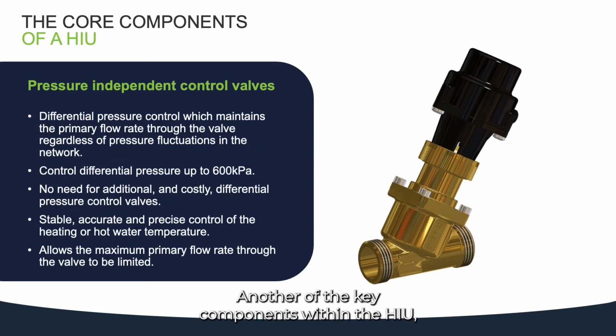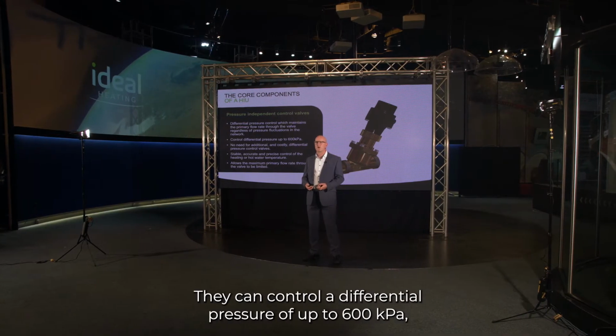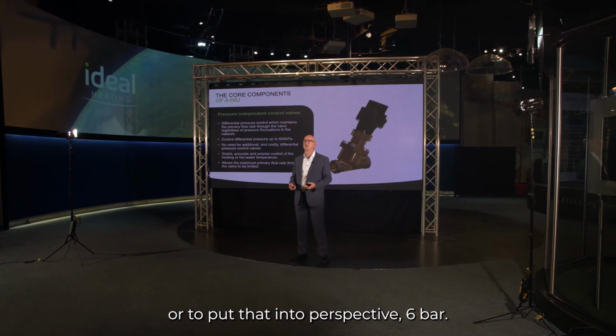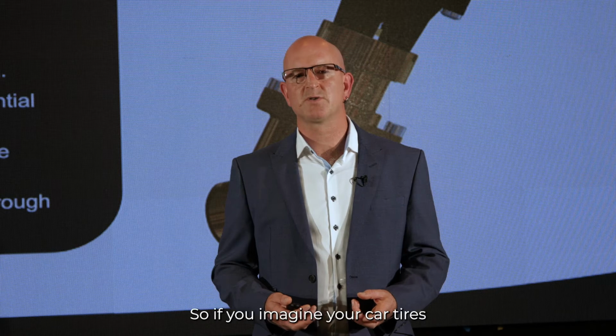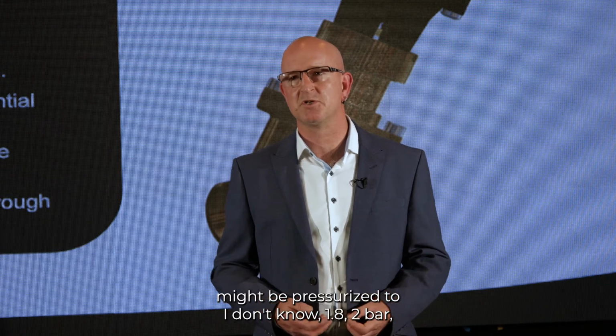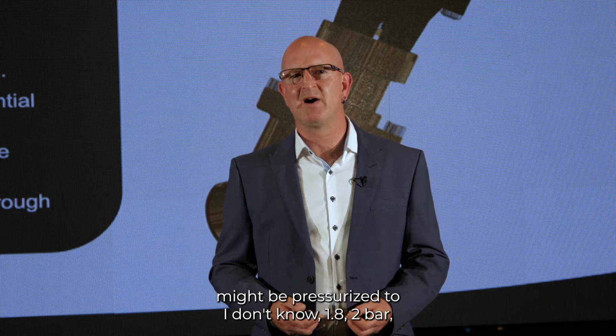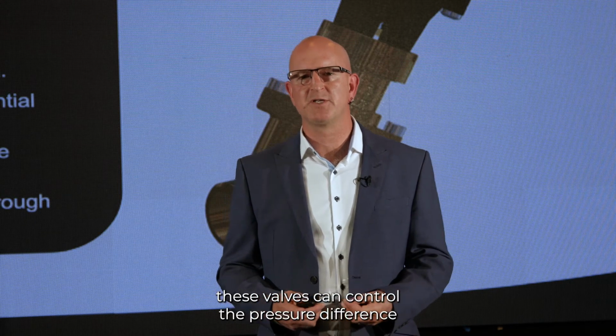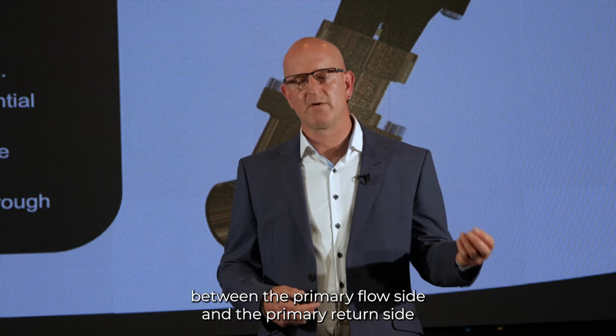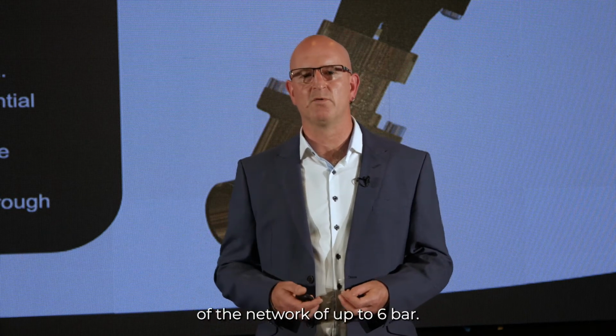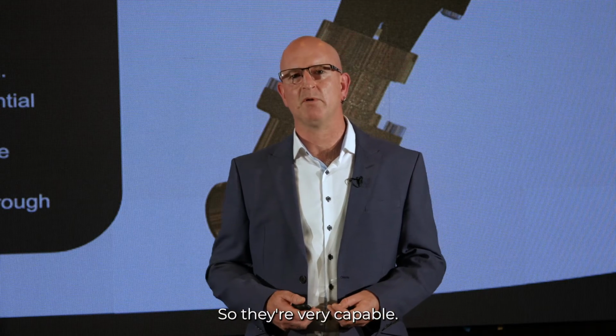Another of the key components within a HIU, generally the pressure independent control valves. These provide the facility to maintain a stable and accurate flow through the appliance under varying pressure conditions on the network. They can control a differential pressure of up to 600 kilopascals, or to put that into perspective, 6 bar. So if you imagine your car tyres might be pressurised to, I don't know, 1.8, 2 bar, these valves can control a pressure difference between the primary flow side and the primary return side of a network of up to 6 bar. So they're very capable.